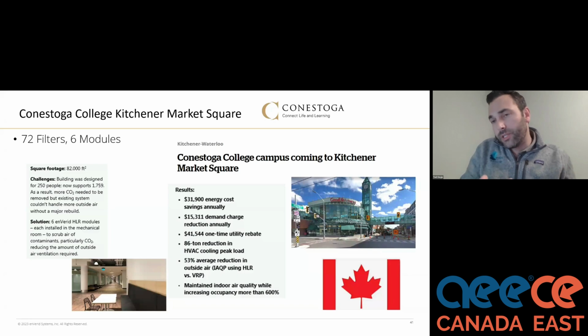And that shopping center was only designed to have 250 people in it. Well, normally you would have to significantly increase the amount of outside air to that space because the occupancy shot up to over 1,700 occupants. Instead, what they did was they deployed 6 of these modules, 72 filters into that space to cut that outside air requirement in half and not have to increase the system on that retrofit application. So this is real practical applications for existing buildings as well as new construction.